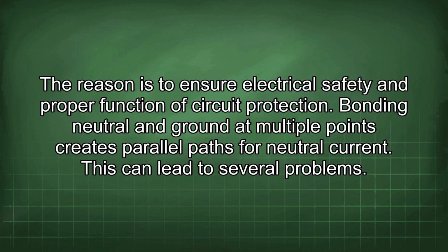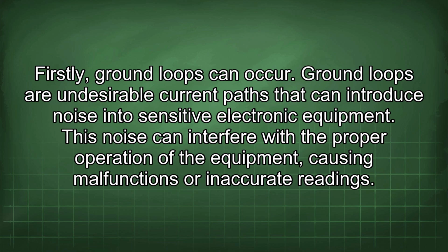Bonding neutral and ground at multiple points creates parallel paths for neutral current. This can lead to several problems. Firstly, ground loops can occur. Ground loops are undesirable current paths that can introduce noise into sensitive electronic equipment. This noise can interfere with the proper operation of the equipment, causing malfunctions or inaccurate readings.